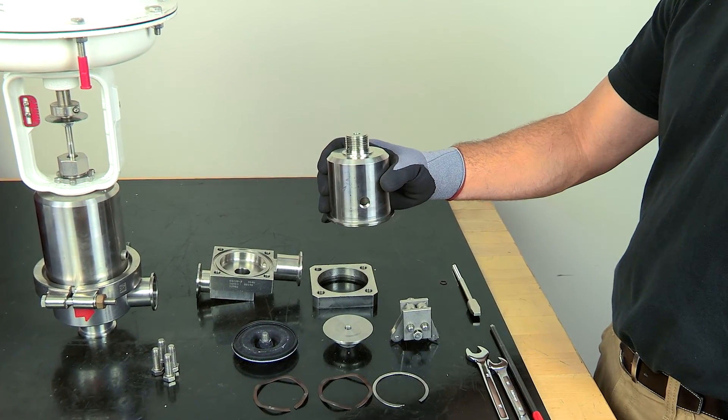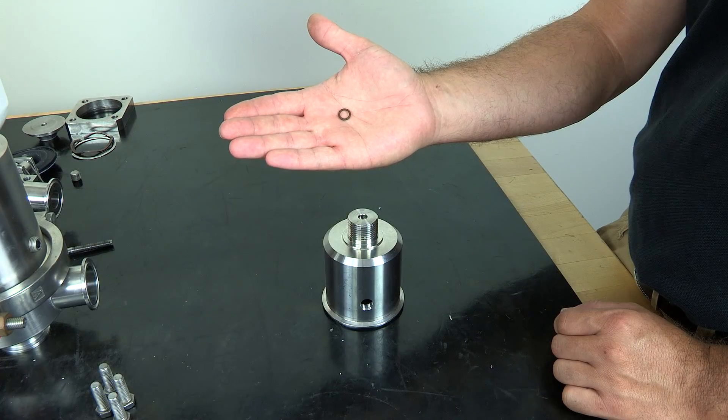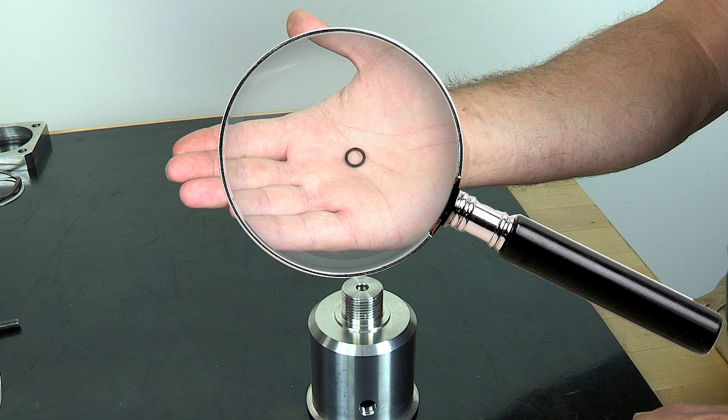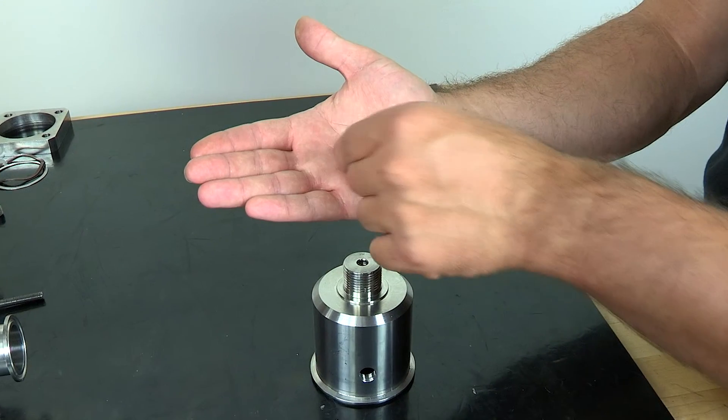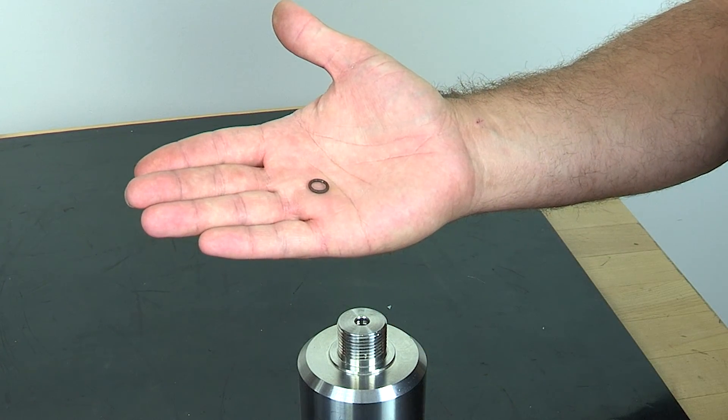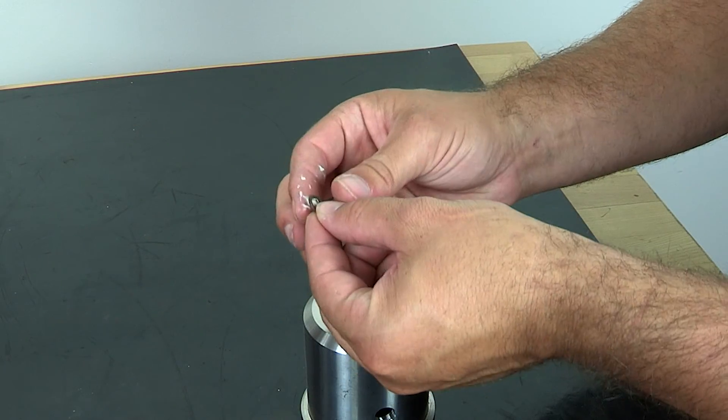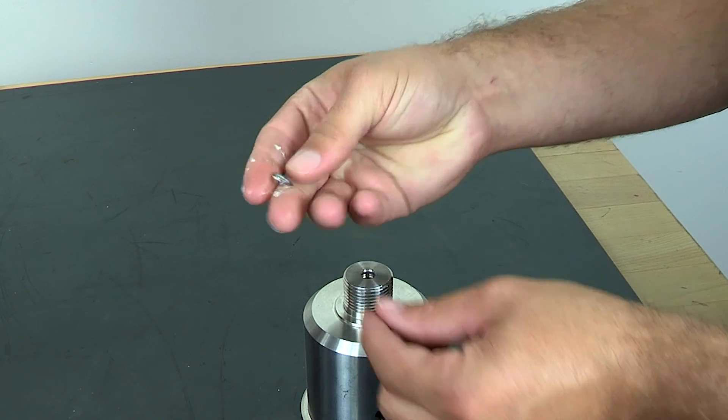First, we'll start with the bonnet assembly. An O-ring is used to seal around the piston stem at the top of the bonnet. Make sure that there are no tears or breaks in the O-ring before installing it and lubricate the O-ring with a sanitary grade grease.